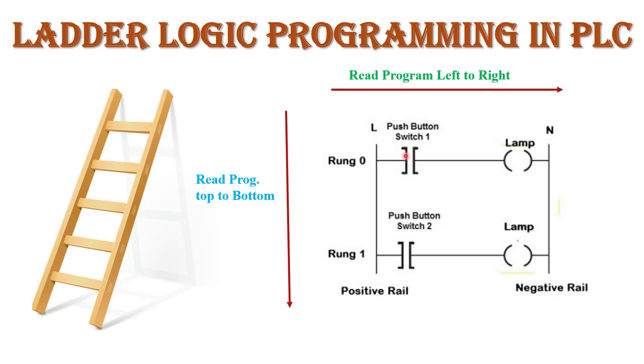In rung 0, the first input uses switch buttons or push buttons, and on the right-hand side we map the output, shown in the form of a lamp, motor, etc. In this way we give input and output instructions in each rung, and the processor of the PLC reads the ladder logic program from left to right and top to bottom. This is the basic concept of ladder logic programming in PLC.